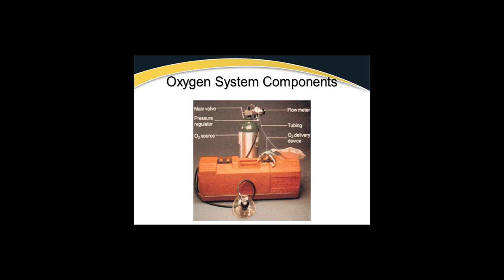Additionally, oxygen bottles are usually green in color or have a green cap over an aluminum cylinder. You can see an aluminum cylinder is the one on page 220. It's spun aluminum, usually has the shoulders, and leading up to the neck is green. The rest of it's silver. While the house tank that they show on 221 is a cast iron or cast steel tank. It is a very heavy tank compared to the aluminum tanks.